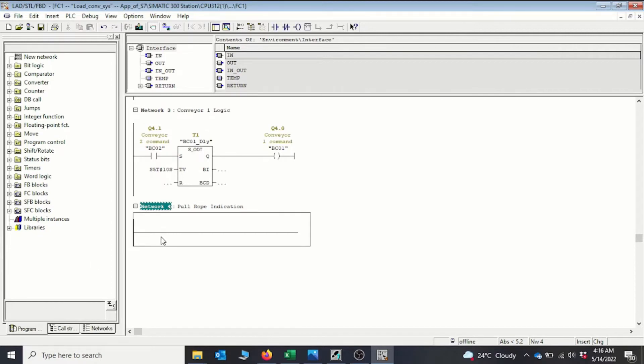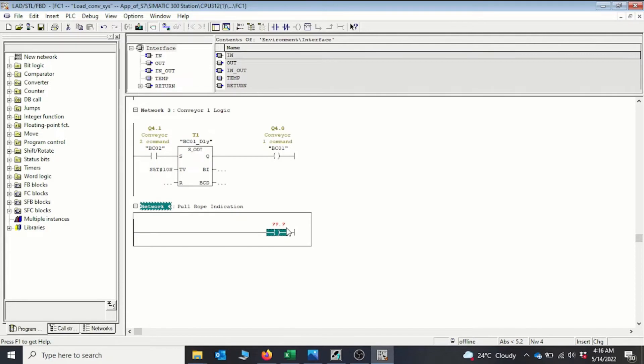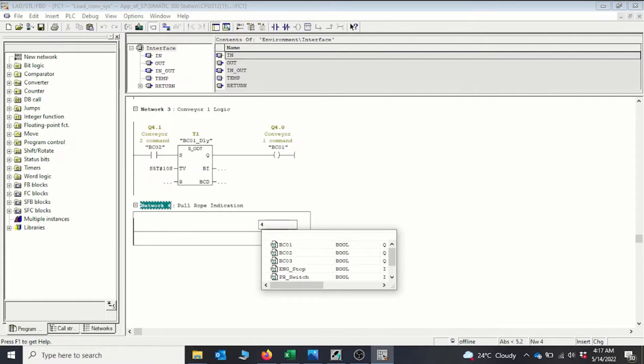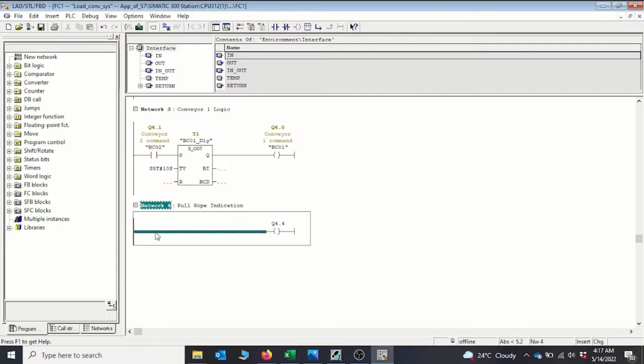We have our pull rope indication network. We'll introduce the pull rope input here. Because we want the lamp to be off whenever the pull rope is not activated, we introduce an output — we'll give it Q4.4, which is not yet used. Then we introduce the pull rope input contact on this network as a normally closed contact, because we want this output to be off whenever the pull rope switch is not activated. This input is I0.3.